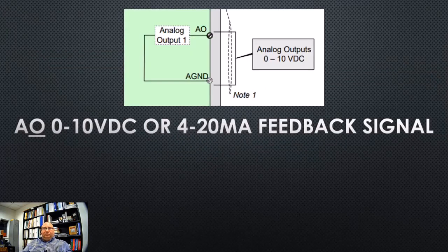We also have an analog output on a drive. This particular drive is allocated for 0 to 10 volts DC. Other drives are configurable. It could be voltage or it could be milliamps. All depends on the model you're going to be using. If you've ever worked on the large McQuay units, when the supply fan activates and runs, it sends an analog output to the return fan. And what it will do is fan tracking. So as the speed increases on the main supply fan, this output from the main drive will go into the input of your second VFD drive, and you could set it to be 1-to-1, or you could set one fan motor to run a little bit higher than the other one, especially with return fans. Also, you could bring this back to the BMS system and have a percentage returning back. So if you told the drive that you wanted 40 hertz, okay, hopefully when you tune it, you get a feedback that it is running at 40 hertz back.